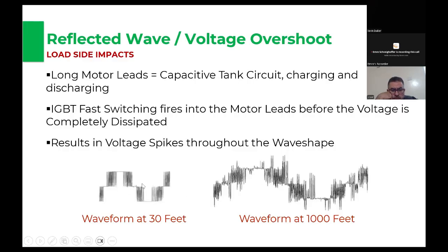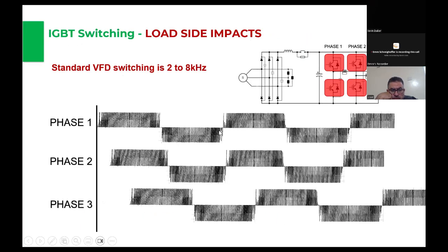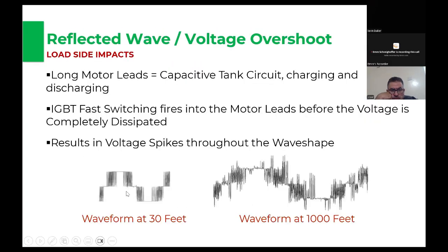So this square wave, which is already a simulated sine wave, now turns into something a little more freakish, and the longer your cables are, the more it distorts. That's because not all the energy is used by the motor, since it's not a pure sine wave. So that energy has to go somewhere, and it ends up reflecting back, adding to the spikes and switches that occur when you chop up this DC signal.